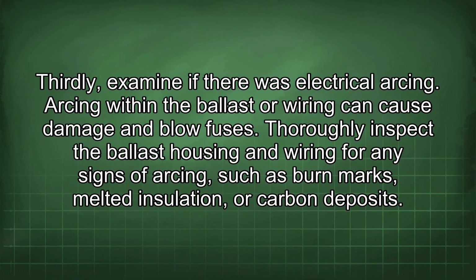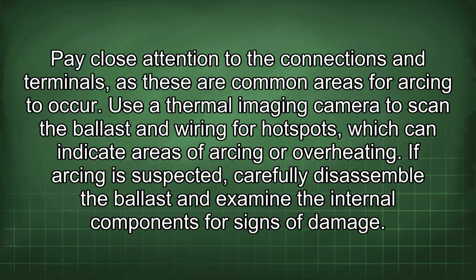Thirdly, examine if there was electrical arcing. Arcing within the ballast or wiring can cause damage and blow fuses. Thoroughly inspect the ballast housing and wiring for any signs of arcing, such as burn marks, melted insulation, or carbon deposits. Pay close attention to the connections and terminals, as these are common areas for arcing to occur.